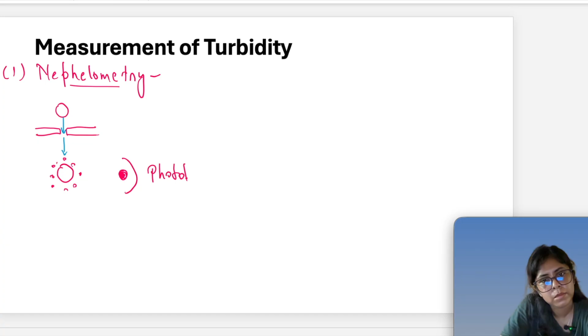Alright, so when the light is incident on the sample, there will be particles there, and the light incident on a particle will be reflected. The light which comes in the 90 degree direction onto this phototube will be captured. So this is the light which is getting scattered. Let's say the incident light is of intensity P, and the light which came out is of intensity P naught. So the ratio P naught upon P determines the turbidity.